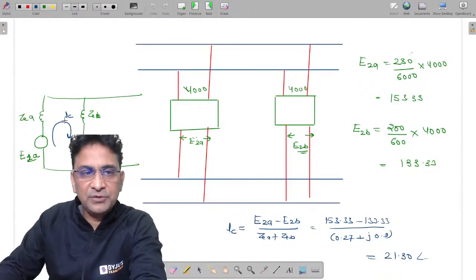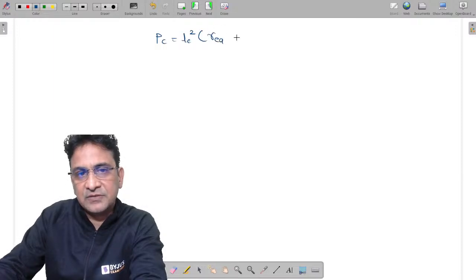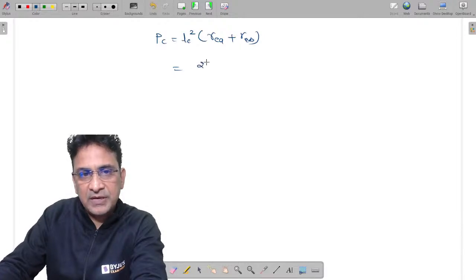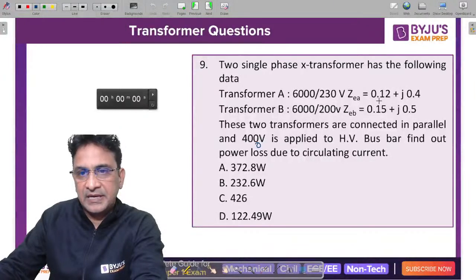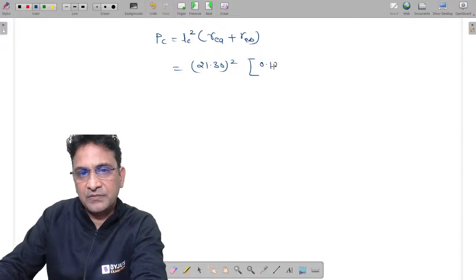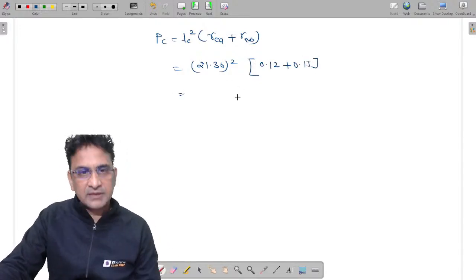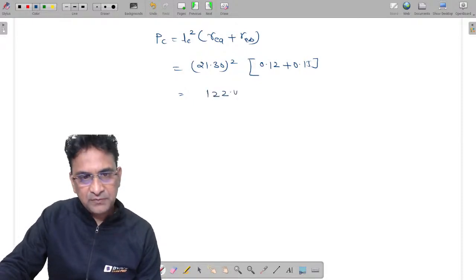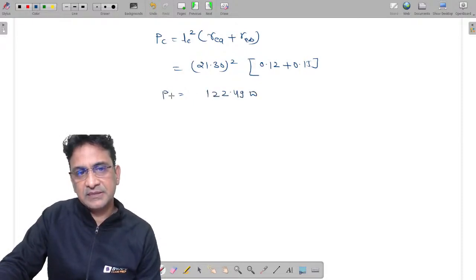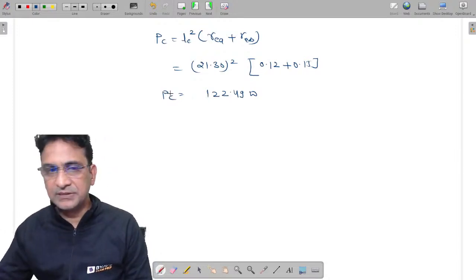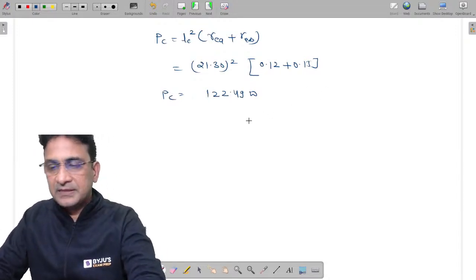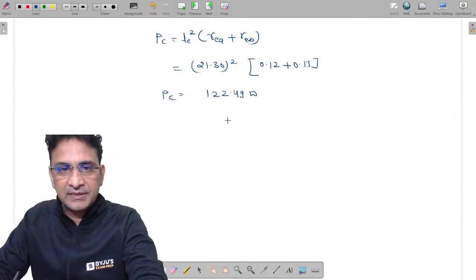Copper losses occur only due to the resistance. So resistance of A transformer and the resistance of B transformer. So 21.30 square, resistance of A transformer is 0.12 and B transformer is 0.13. 0.12 plus 0.13. So if you calculate, it will come 122.49 watt. This is the extra power loss that takes place due to the circulating current. Is it clear?